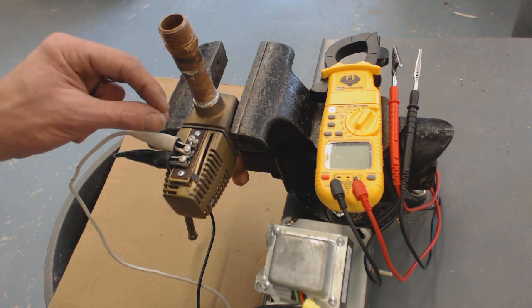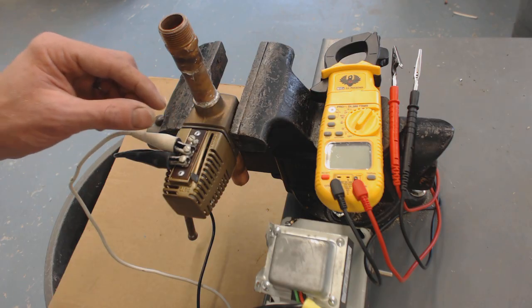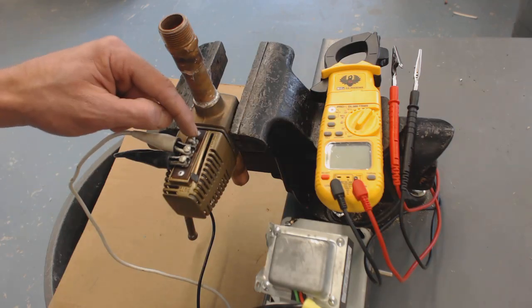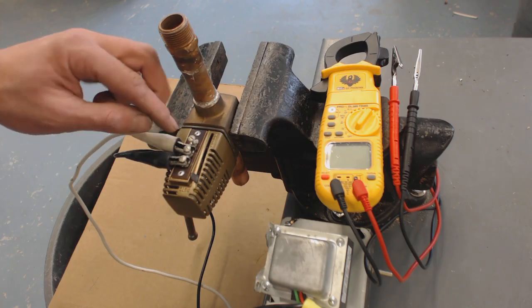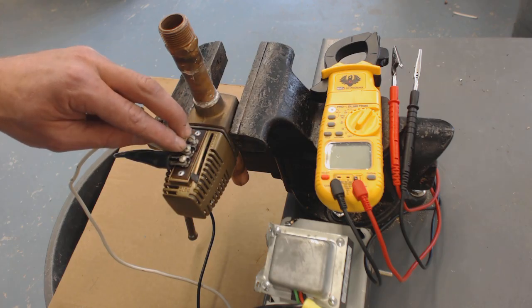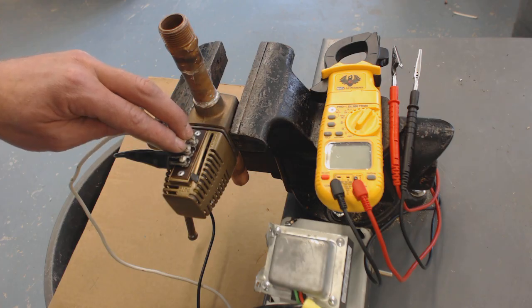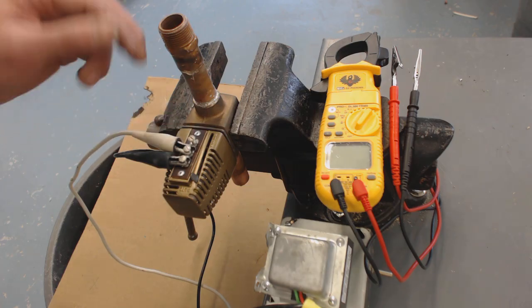Once it's opened it up, it hits a little micro switch inside and presses that in. What it does is it closes this end switch, number three, with number two. So when it closes this switch right here, that's going to tell either the control board or the Aquastat relay to turn the circulating pump on.